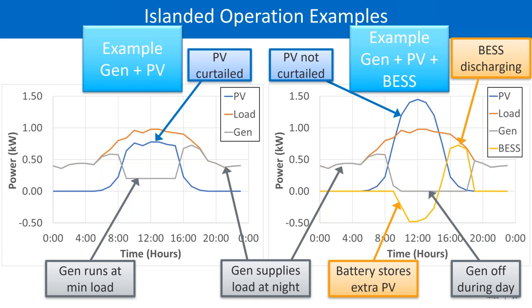So you can see the power for the battery storage actually goes negative because it's being charged, so it gets charged in the middle of the day. Then after the sun starts going down, the battery starts discharging. The generator stays off because it's still not needed. Eventually the battery is discharged and it would transition over to the generator, which would run the rest of the night.